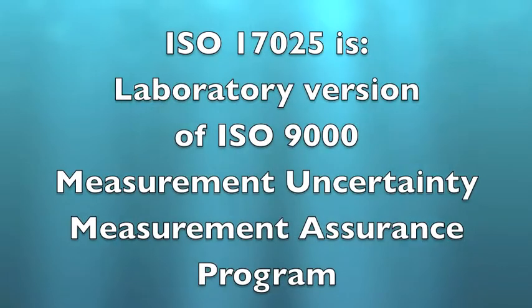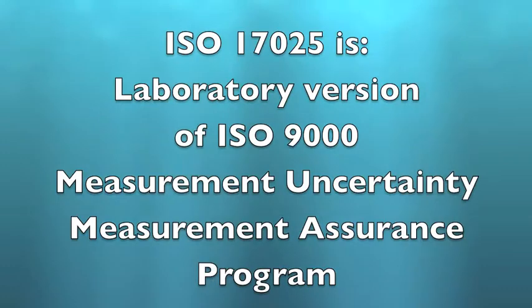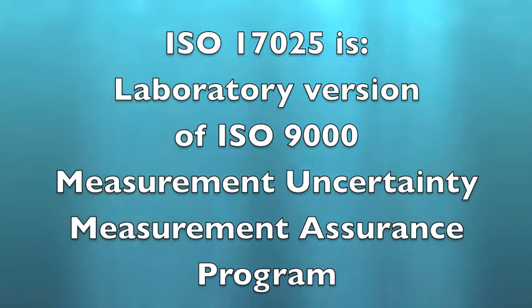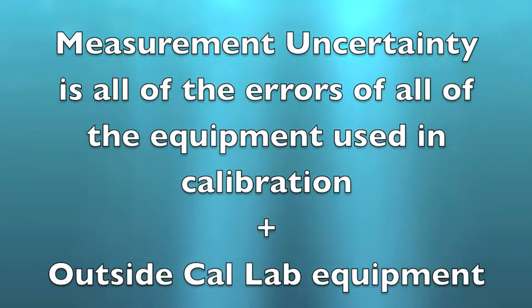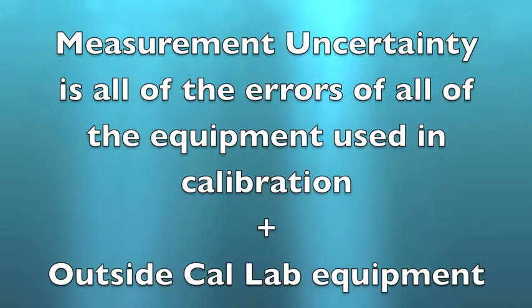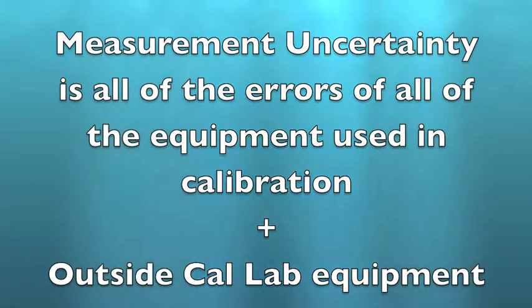You have learned that ISO 17025 is a laboratory version of ISO 9000 that emphasizes calculating the measurement uncertainty of all measurements made in calibrations and tests, as well as having a measurement assurance program. You have also learned that measurement uncertainty calculates all errors for all equipment used in the calibrations, traced all the way to the international standards of measurement, including outside lab equipment and any other equipment used by any other lab in the chain.